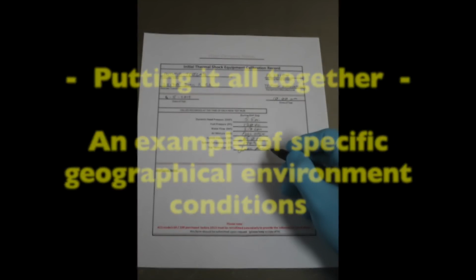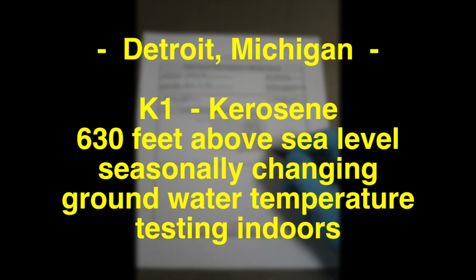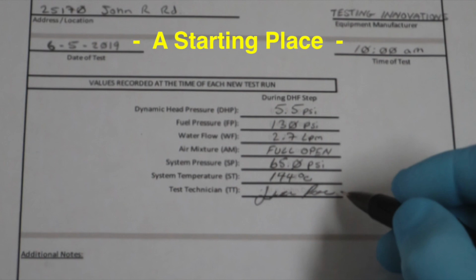Remember that Detroit, Michigan is approximately 630 feet above sea level with a normal annual temperature range of 0 degrees F in the winter to 90 degrees F in the summer. If you are in a similar location, the values that you see on your machine should be similar. A calibration certificate with values from Detroit, Michigan using K1 kerosene is provided with each unit and should function as a guide to performing calibrations.